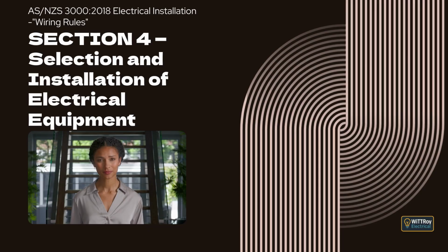It also explains that socket outlets must be installed so plugs do not loosen or malfunction due to gravity, vibration, or cable weight, and that where socket outlets are not readily accessible and are used for fixed appliances or luminaires, they must be securely fixed to prevent strain on the wiring during plug insertion or removal, with stated exceptions where mechanical stress is already adequately controlled by the wiring system and its support. It further explains that socket outlet use is restricted in damp locations, hazardous areas, and other special situations, and that where socket outlets are installed in fire-rated or acoustic building surfaces, their protective properties must be maintained.